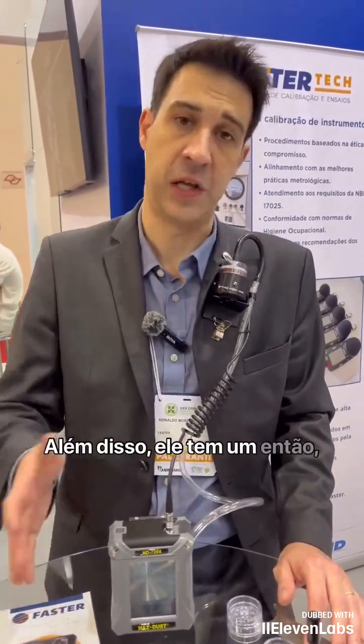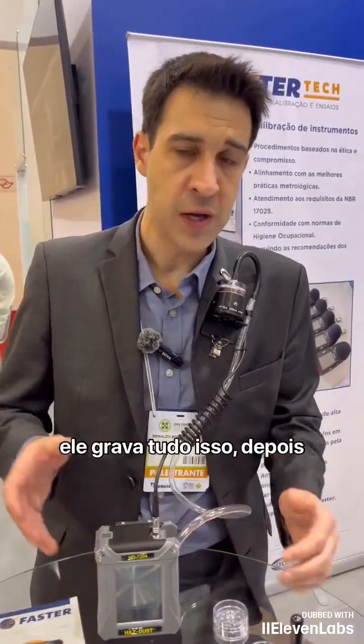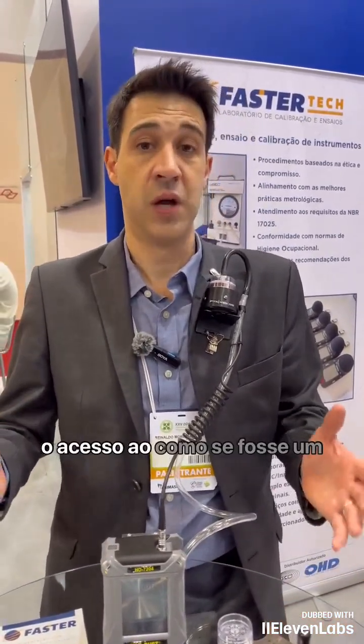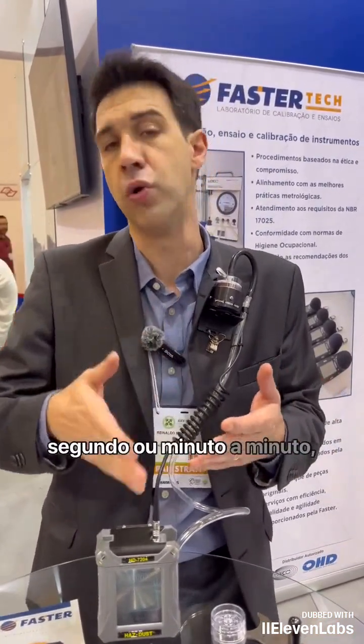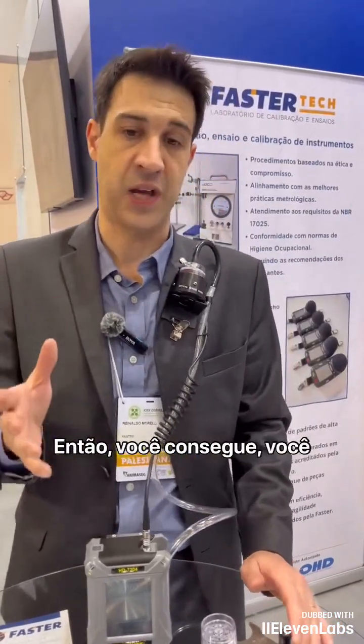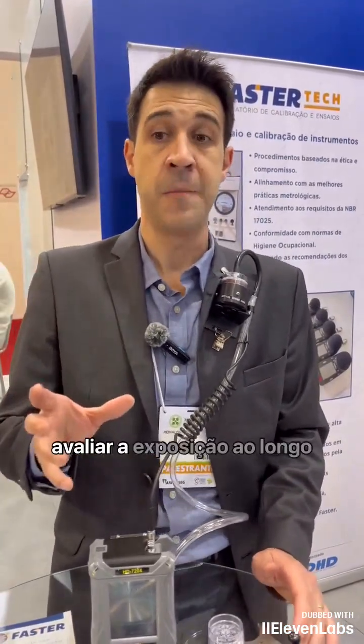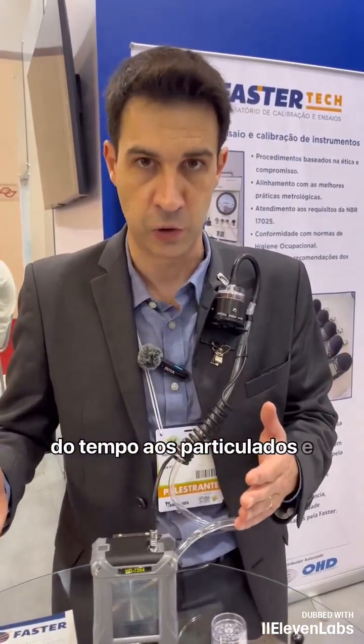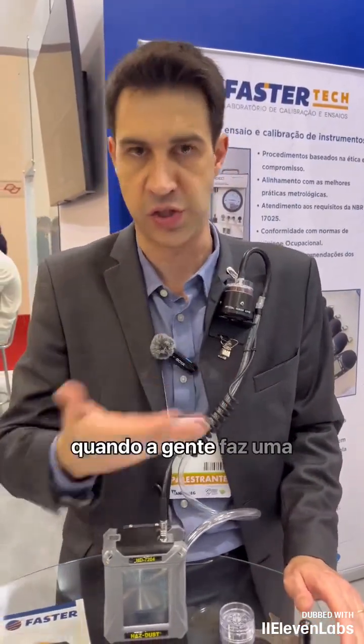Additionally, it has a data logger, so it records all this information. Later, you can use the software to download this data and access a histogram, second by second or minute by minute, just like we already use with a dosimeter, so you can assess the exposure to particulates over time and not just a single result, which is what we get when we do a normal evaluation and collection with a cassette.